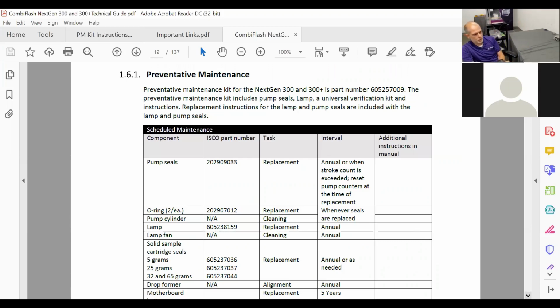So the part number for a PM kit for a NextGen 300 or 300 plus is 605-257-009. The PM kit for a NextGen 100 is the same part number ending in 10 instead of 09. And in that kit, you're going to get new pump seals, a new lamp. You're going to get a universal verification kit, which is test mix. It's a standard. We know what kind of peaks and the generalized time in which those peaks are supposed to come off. We know the generalized shape of what those peaks are supposed to be.